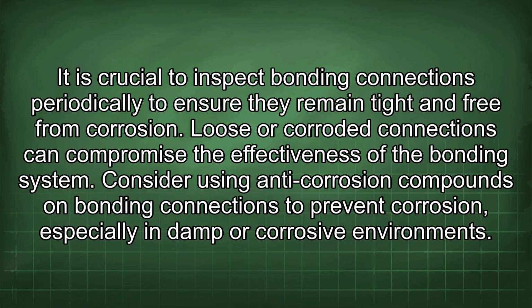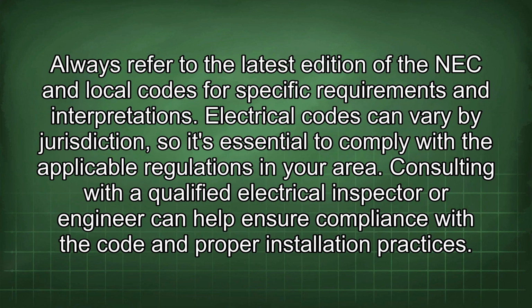It is crucial to inspect bonding connections periodically to ensure they remain tight and free from corrosion. Loose or corroded connections can compromise the effectiveness of the bonding system. Consider using anti-corrosion compounds on bonding connections to prevent corrosion, especially in damp or corrosive environments. Always refer to the latest edition of the NEC and local codes for specific requirements and interpretations. Electrical codes can vary by jurisdiction, so it's essential to comply with the applicable regulations in your area. Consulting with a qualified electrical inspector or engineer can help ensure compliance with the code and proper installation practices.